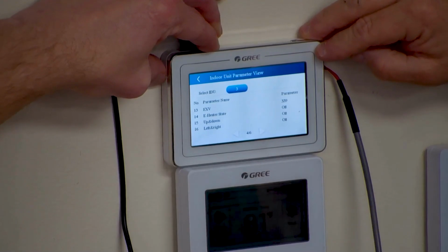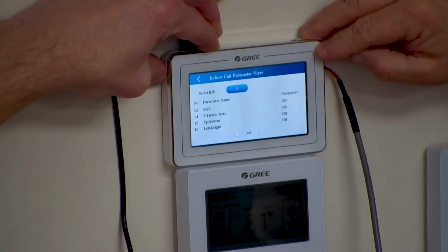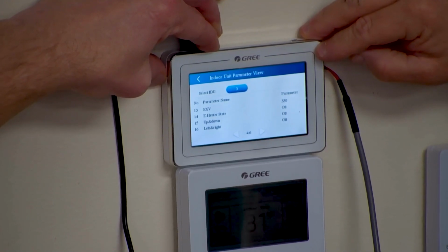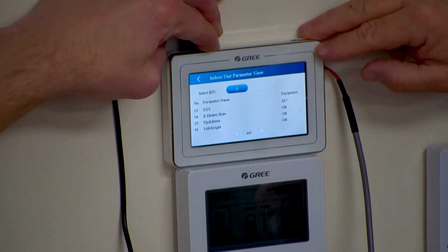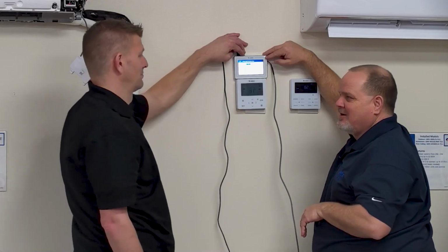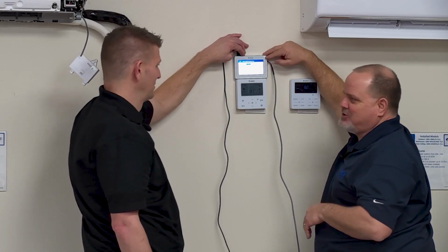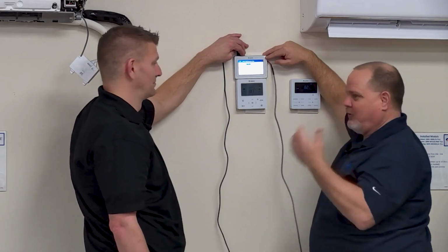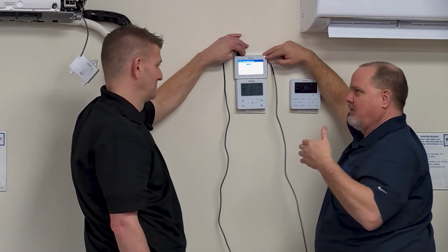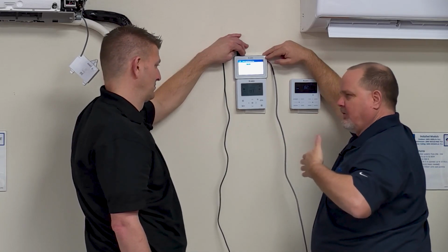EXV step 339. Remember, this is going to be fairly open anyway, because when I said that EXV is really calling, and you step back and actually think about it for a minute: wait a minute, I'm in heating mode, I want to open it up. I want to get good flow through there, because that's my discharge line, right? Yep. I'm trying to flow. I'm flowing in through my discharge line, which would be my inlet of the coil.